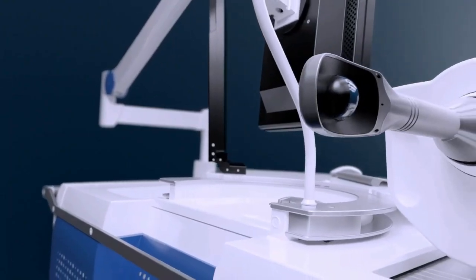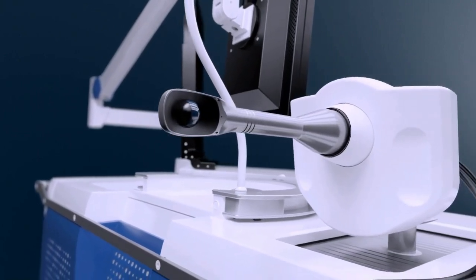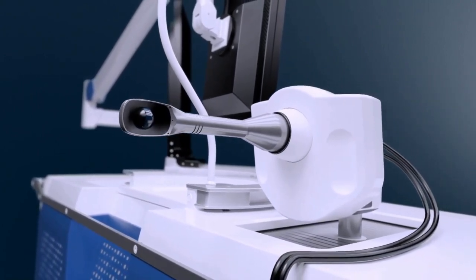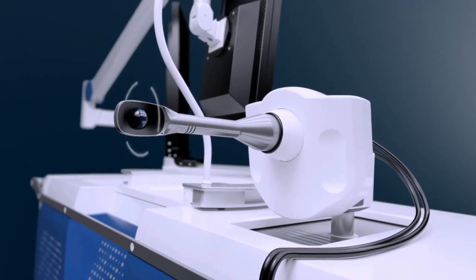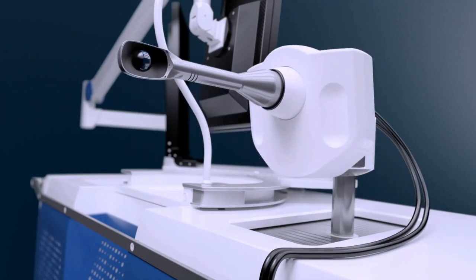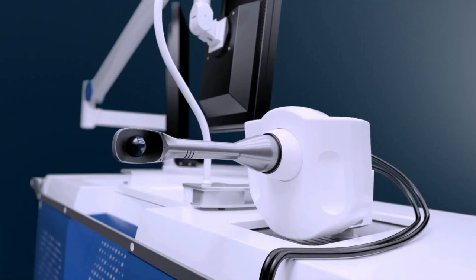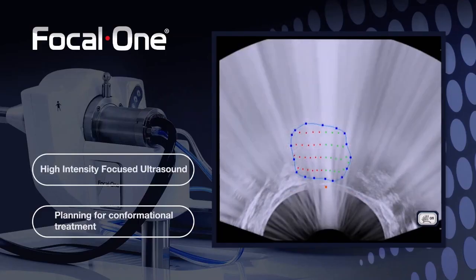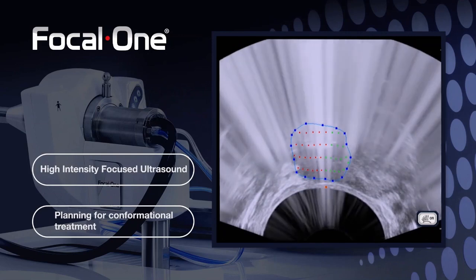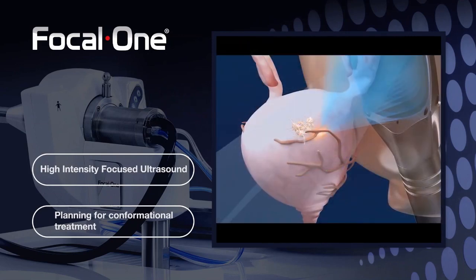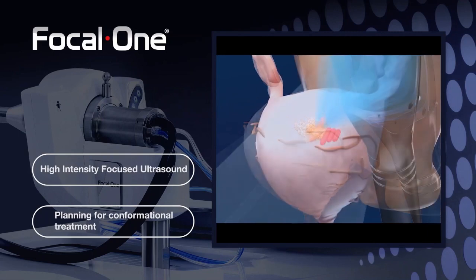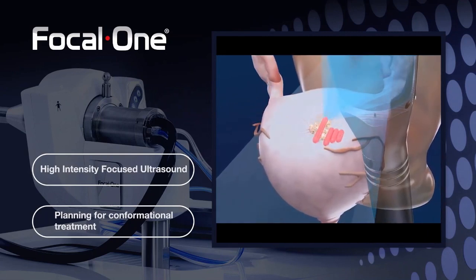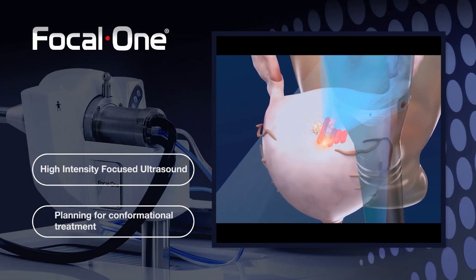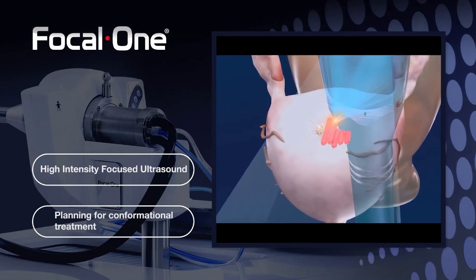This is the dynamic focusing probe. It allows for real-time imaging, with the highest quality ultrasound imaging transducer on any HIFU system. The probe has 5 degrees of freedom and can ablate up to 30 cc of tissue per hour. So a focal case usually takes about 45 minutes, with a hemi taking about an hour. It allows precise energy delivery in 5 mm increments up to 40 mm in anterior to posterior length, expanding the distance previously available. The system constantly monitors the position and temperature of the rectum. The algorithm is able to move the probe with the prostate, maintaining the perfect position without manually adjusting the probe.